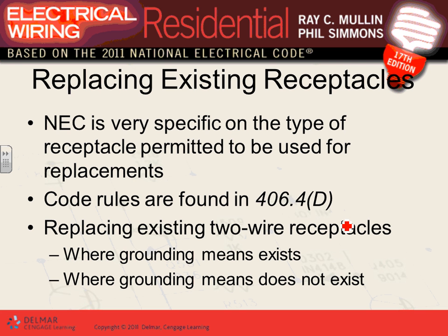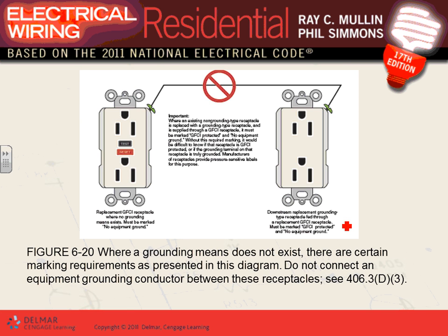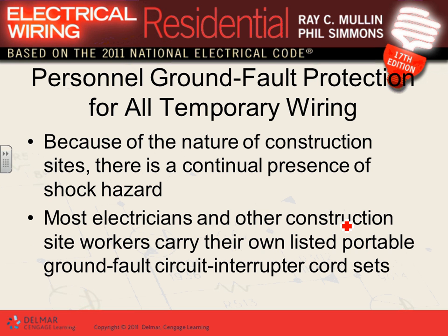Now, if you're replacing non-grounding type receptacles, there are a few rules, guys. If you have an old-days non-grounding receptacle, you can replace it with another non-grounding receptacle, with a GFCI, or with a grounding receptacle fed from a GFCI and labeled with no equipment grounding conductor. So these are a few locations where you can replace. I have a couple of pictures that you guys will look at.